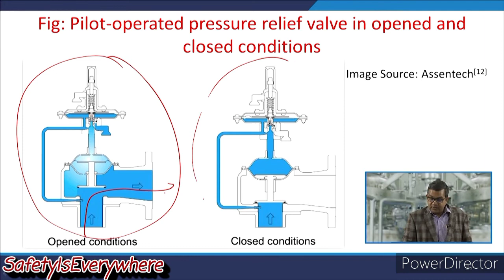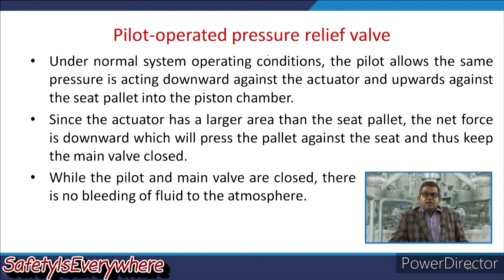They are here. Under normal operating conditions, the pilot allows the same pressure, which is acting downward against the actuator and upward against the seat pallet, into the piston chamber. Since the actuator has a larger area than the seat pallet, the net force is downward, which will press the pallet against the seat and thus keep the main valve closed. While the pilot and the main valve are closed, there is no bleeding of fluid to the atmosphere.